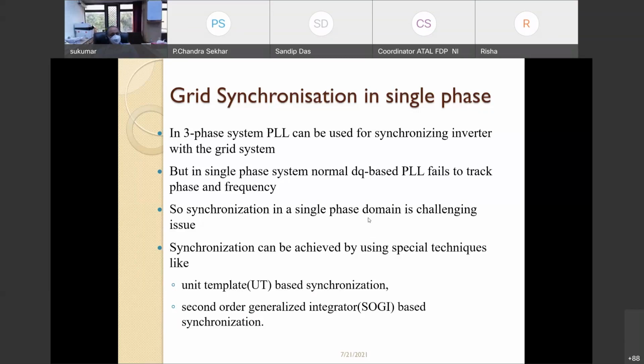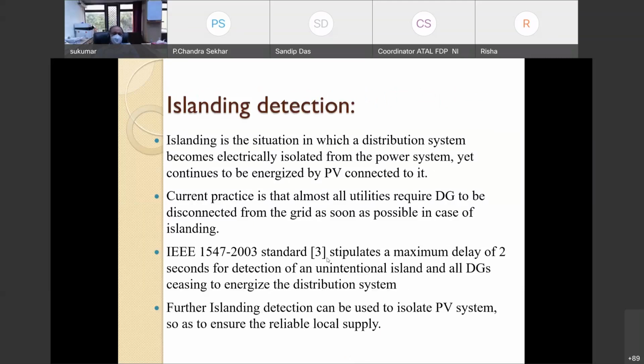However, there can also be an alpha beta based approach where we can go for a single phase synchronized PLL. Apart from that, there has to be islanding detection in your grid connected operation, because we do not know where the grid will fail, and there could be an intentional islanding or an unintentional island. If it is an unintentional islanding and your inverter starts feeding power to the grid, then the person who is in operation of the grid may die. Hence, islanding detection is a must.